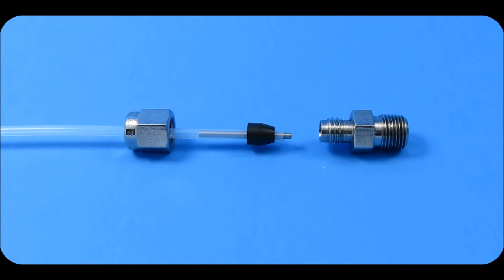The system is made up of four components. The first component is a standard stainless steel instrumentation quality compression fitting. There are a variety of brands such as Swagelok, Bylock, and Parker and any of these can be used in our system.